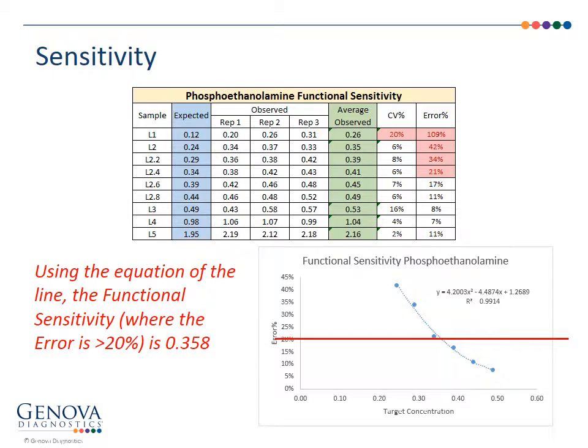That makes sense. We don't like to do it mathematically like this. This is totally legitimate. CLSI is fine with it. But we find this is really hard, once it's in production, to actually maintain, because you're going really down to the bleeding edge of that assay. Is it reproducible? Yeah. Is it difficult to run CalVARs all the way down there? You betcha. So unless it's something that's really clinically valid, we typically just go with the functional sensitivity levels as shown above.